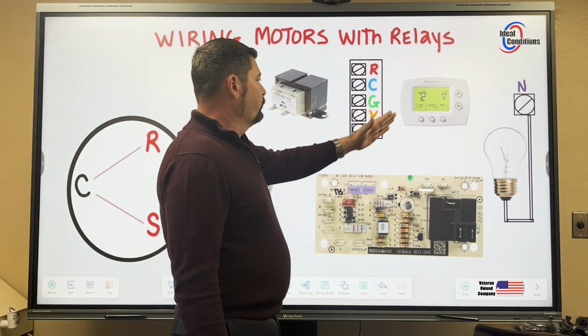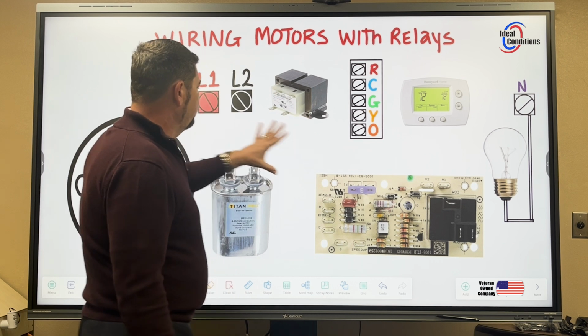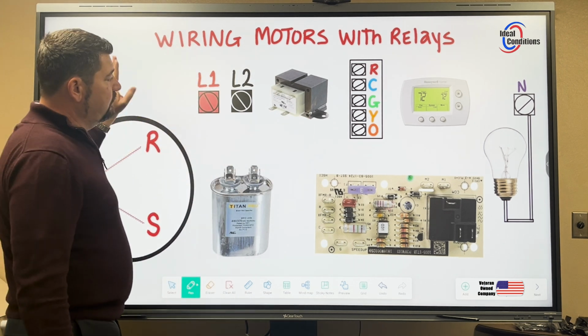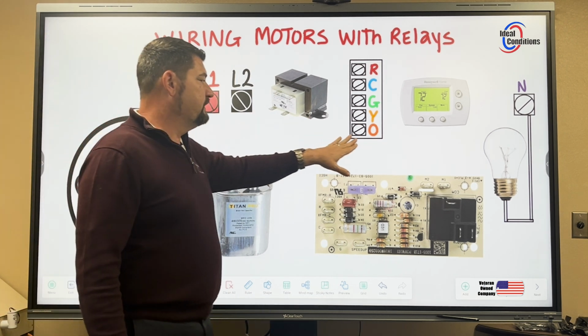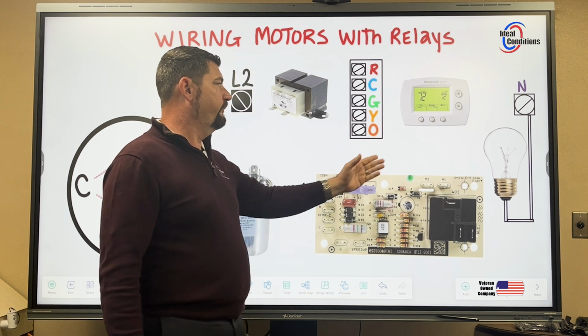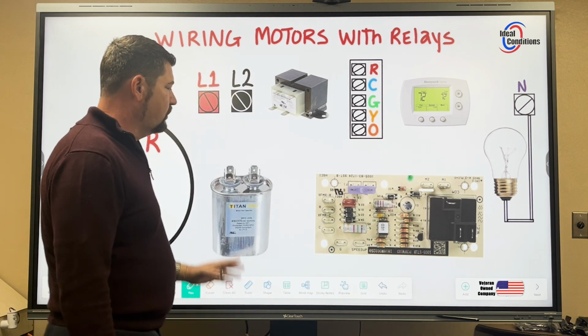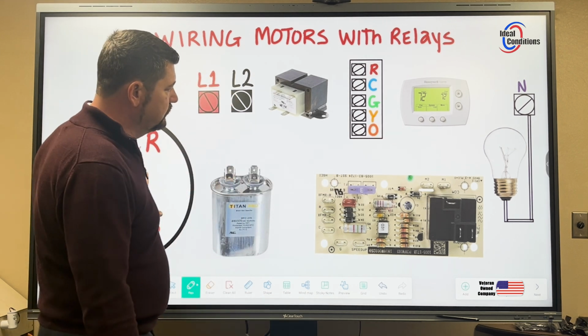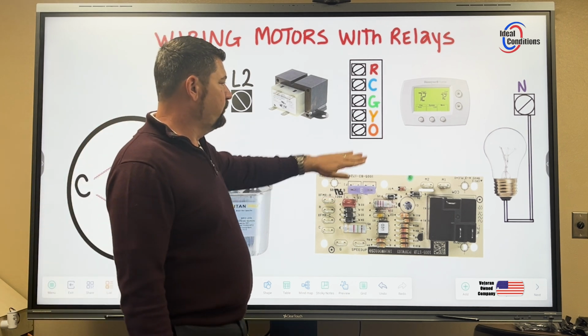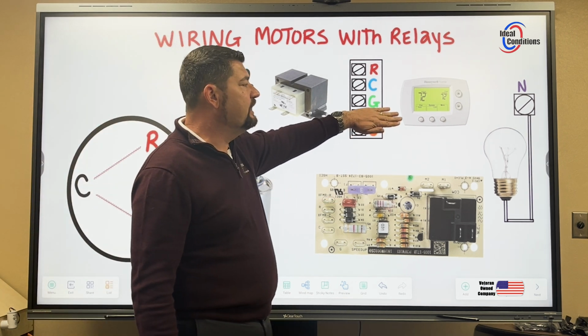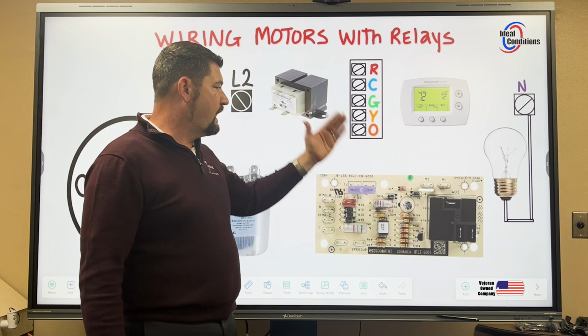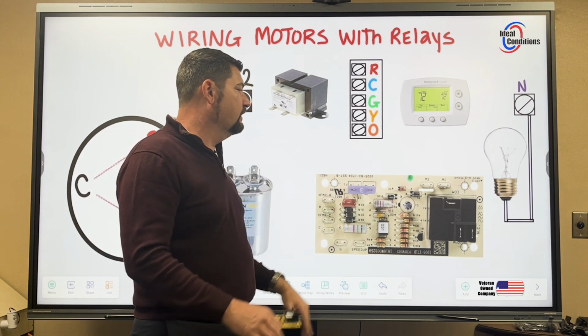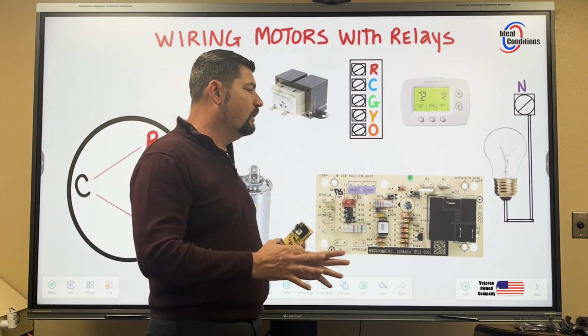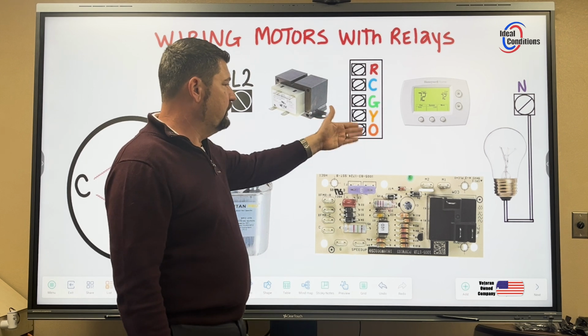We have a low voltage terminal block, the thermostat. I don't have a float switch here. I don't have heat strips here. I don't have even a W wire for heat. Our focus is on the fan motor, and the only terminals that I really need are the R, C, and G. I just put the Y and the O there because I wanted to make everything at least one stage. This is one stage heat, one stage cool.